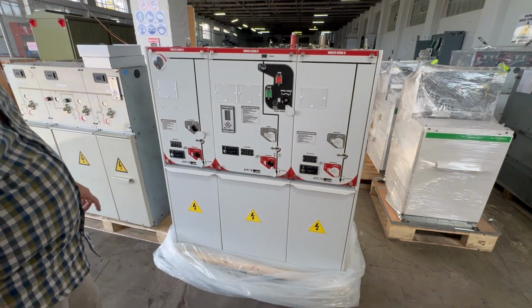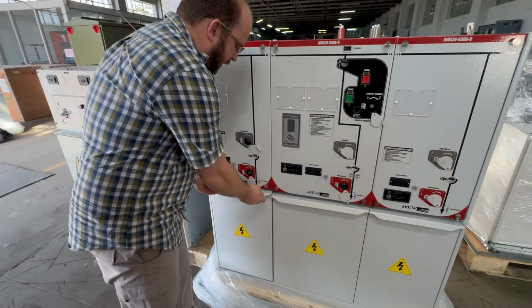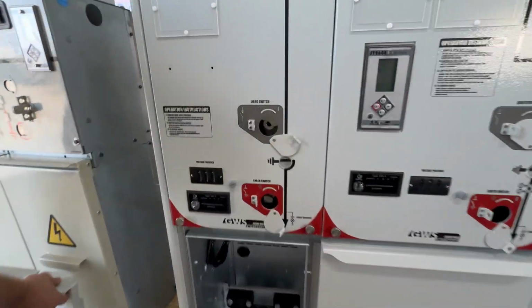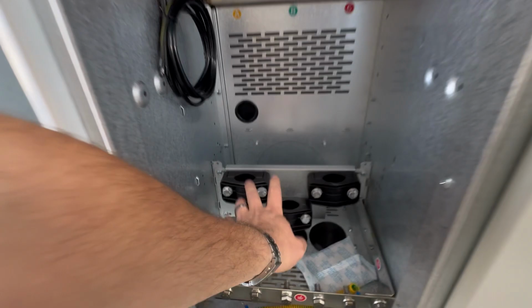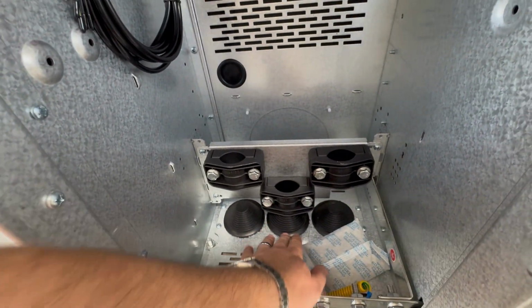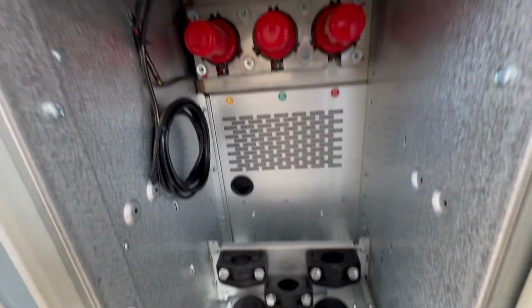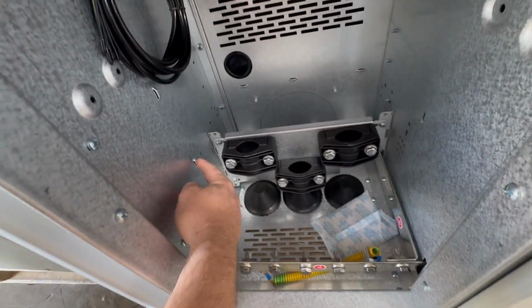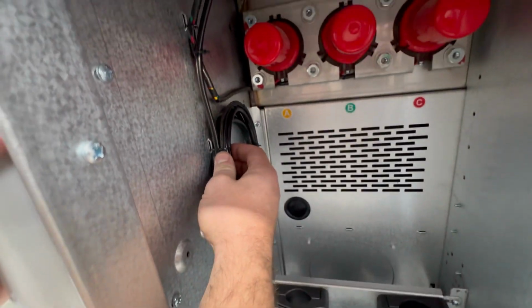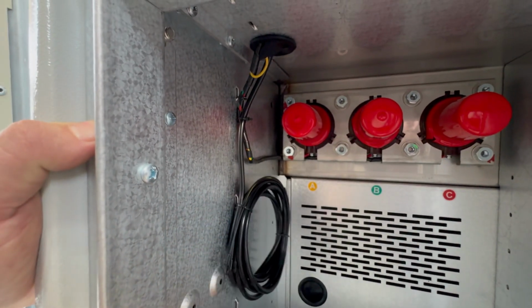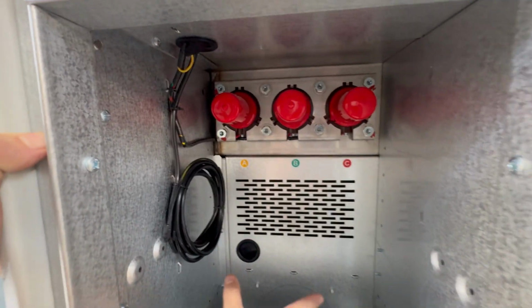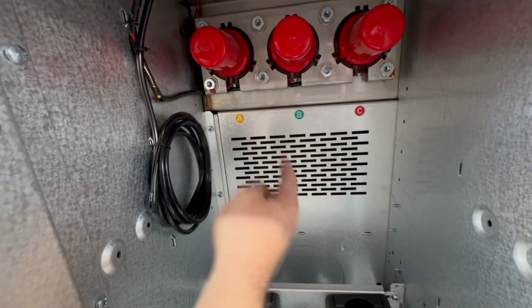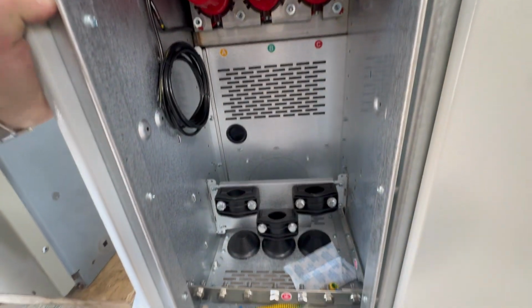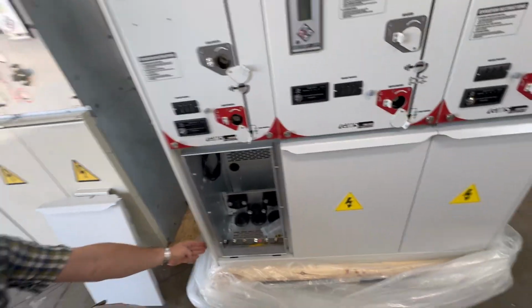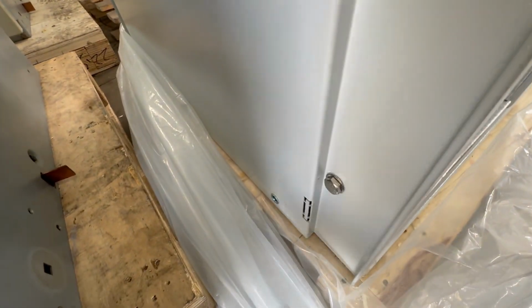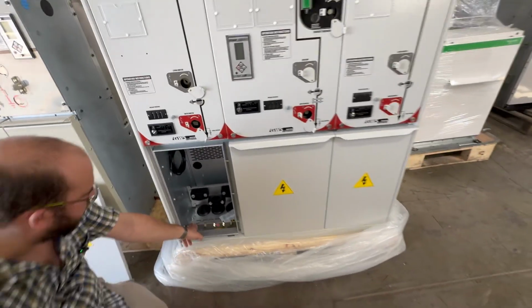Let me show you in the cable chamber. So while it is on earth, I can open the cable chambers and show you what goes on inside. So inside you can have 3 wires or a 3-core cable coming in, or you can have a single core coming through the middle. You have got your earth bars. You've got these nice stubs where you can fasten your LV cables so they are sturdy and nice. You can see there, no more sticky feet. And you've got the X-flow vent to the back. And here you can also see grommets and all kinds of connectors to take you to places. On the side, you can see the earth preparation being done for connecting earth from the outside, if that is what you want to do with the earth bar.